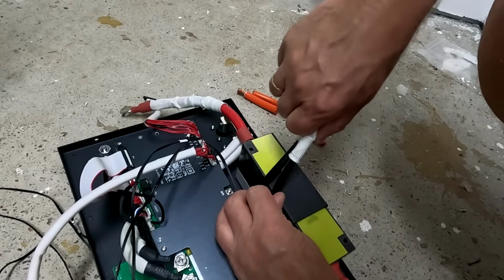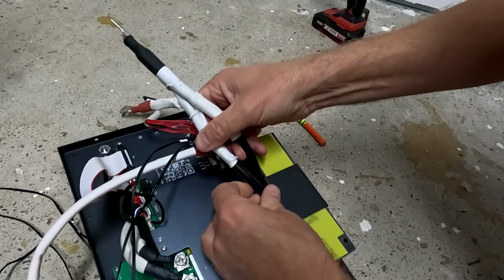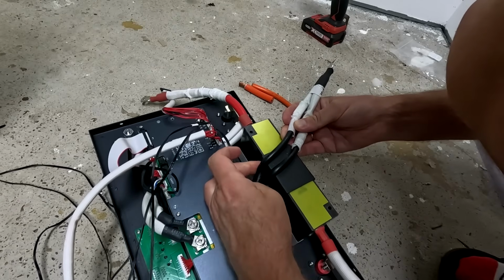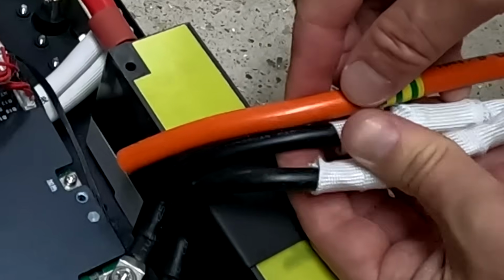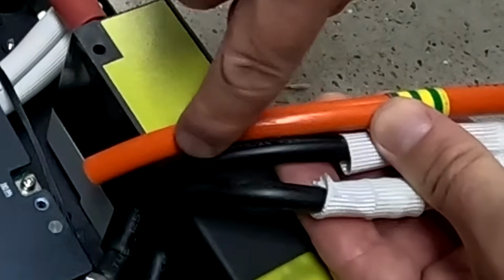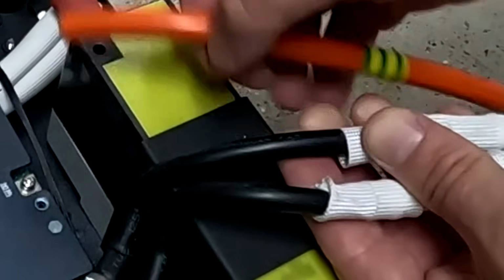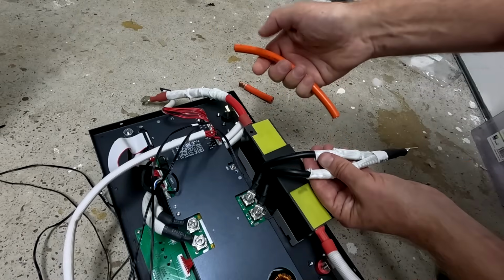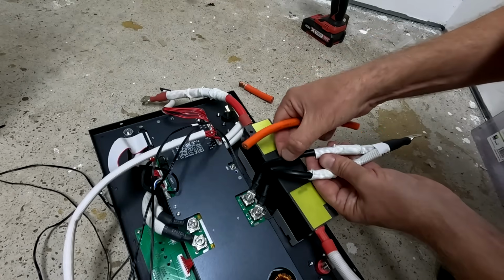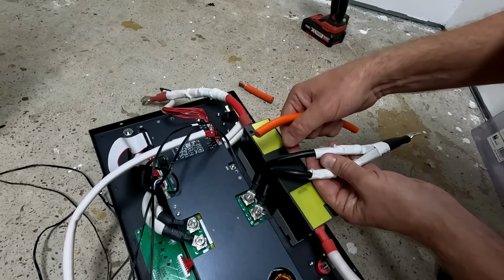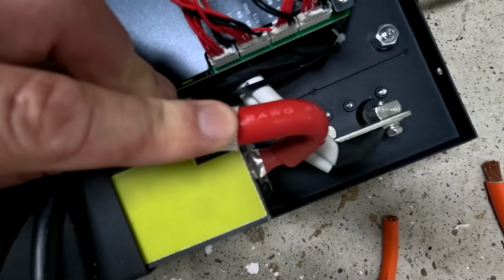I am trying to find a cable size, somehow an identification for these cables. Yeah, it doesn't tell us what cable size this is, but this is a 16mm cable, double insulated, and this is definitely a bit thinner, but I think this is only single insulated cable here, which is not great anyway. So we probably deal with a 2 times 16 square millimeter cable, and the big one to the breaker actually shows us a 2 American wire gauge. So a 2 gauge wire is around 33 square millimeters, and a 35 millimeter cable, which is this size here, is good for around 120 amps conservative. Depending what table you take, I always take the conservative one, 120 amps.